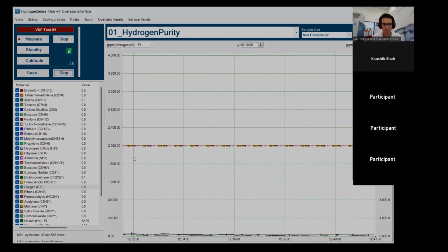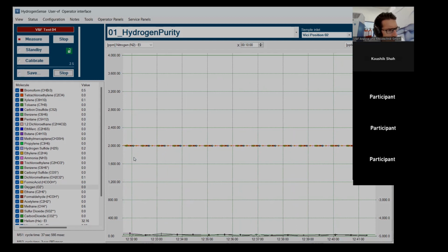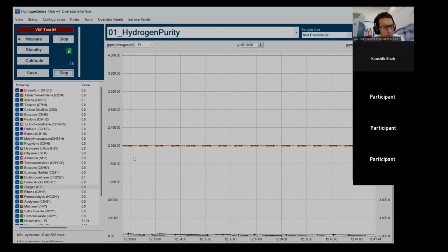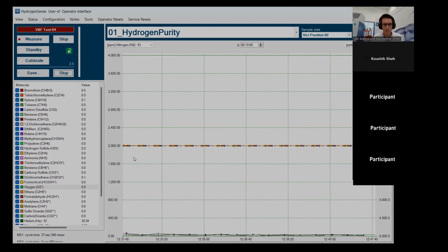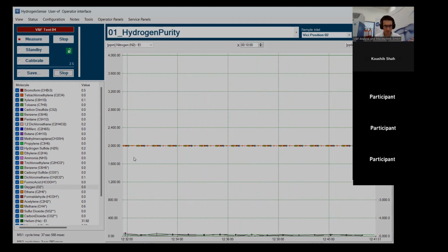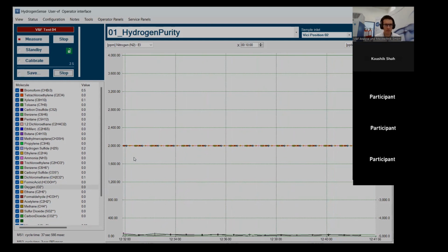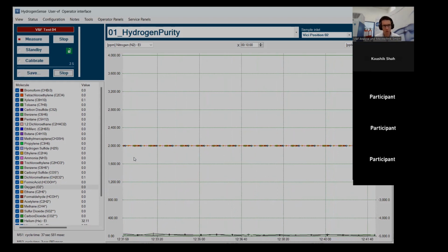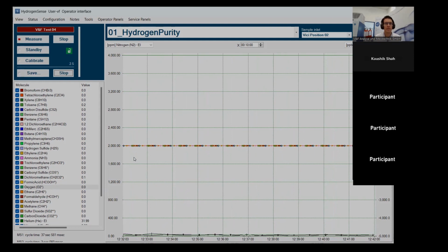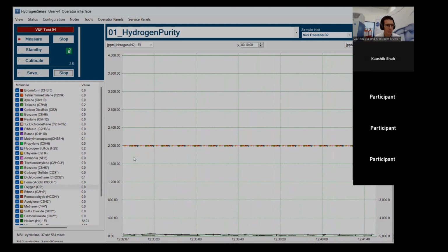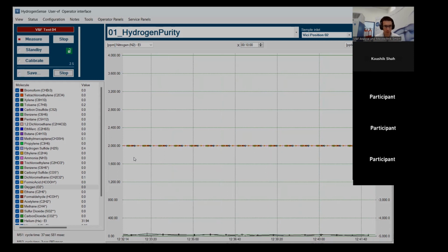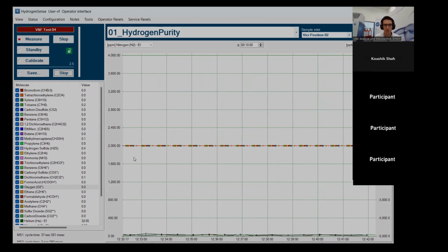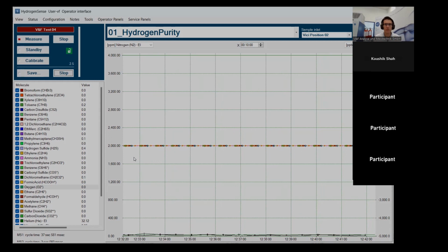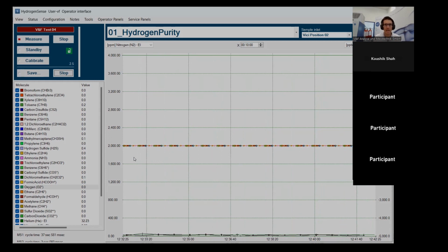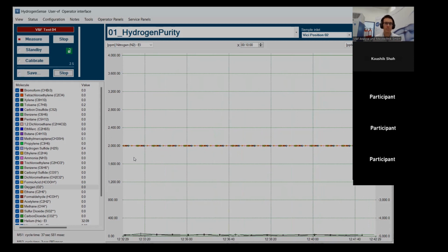Okay, and your system is safe from any such contaminant? The hydrogen sense, it is safe from any such presence of moisture in the hydrogen. Yeah, the moisture is not an issue. You can pretty much run multiple volume percent of moisture into that instrument. The thing is, for our technology, the very low levels required, which are currently 5 ppm, are not something that we can reliably quantify using the IMR-MS principle. That is why we're using an auxiliary device. But in principle, the instrument can detect moisture, and it's also possible to have loads of moisture in the instrument. What we always need to take care of is that it is non-condensing moisture. So it needs to be gas phase moisture in order to be analyzed. Okay.